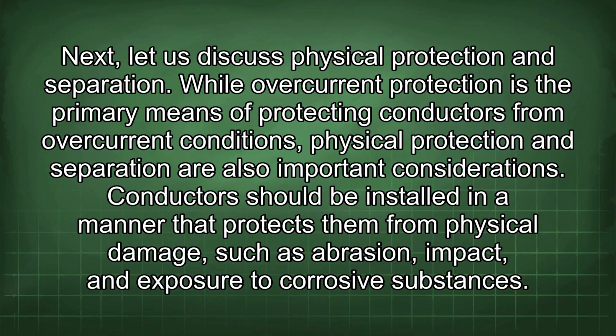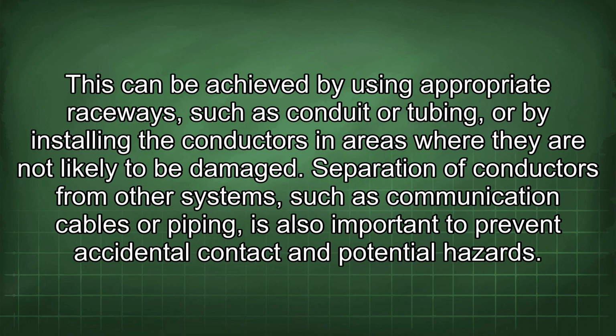Next, let us discuss physical protection and separation. While overcurrent protection is the primary means of protecting conductors from overcurrent conditions, physical protection and separation are also important considerations. Conductors should be installed in a manner that protects them from physical damage, such as abrasion, impact, and exposure to corrosive substances. This can be achieved by using appropriate raceways, such as conduit or tubing, or by installing the conductors in areas where they are not likely to be damaged.